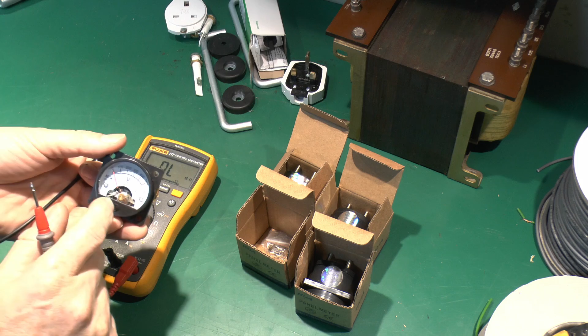These are actually marked plus and minus, but for AC it won't matter, though it may matter for testing. So let's connect up the minus and the plus, and we should see a fairly high resistance here. Seeing about 2.8 megaohms, that doesn't seem too bad. Let's see what it does in the other direction. Yeah, it's actually open in the other direction, so there's presumably some diode or something inside to rectify, because although this whole assembly is rated for AC, the meter movement itself won't work on AC, it will be DC only. So that's fine for that one.